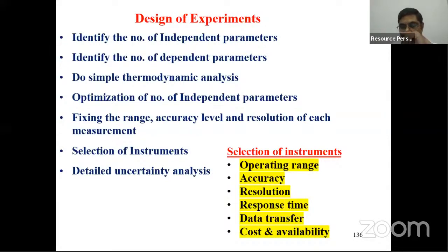How should instruments be selected? Instrument selection should be based on the operating range—for temperature, what range you are going for. Then, what level of accuracy do you want—plus or minus 1 degree Celsius or plus or minus 2 degrees? What is your required resolution? And what about response time—do you need a fast response, slow response, or dead slow response? You need to determine this.